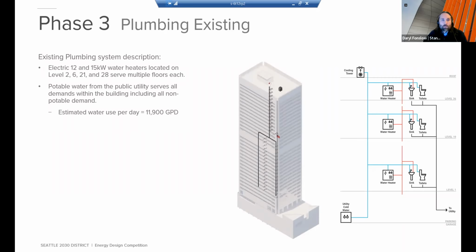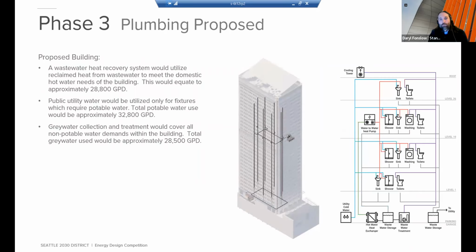Shifting into the proposal, we added heat recovery to this system on the wastewater side, as well as a gray water system. The gray water system serves to provide water for toilet flushing, residential washing, and cooling tower makeup water. We were able to eliminate electric water heating, with heat recovery from the wastewater system supplying all the hot water demands for showers, sinks, and residential washing machines.